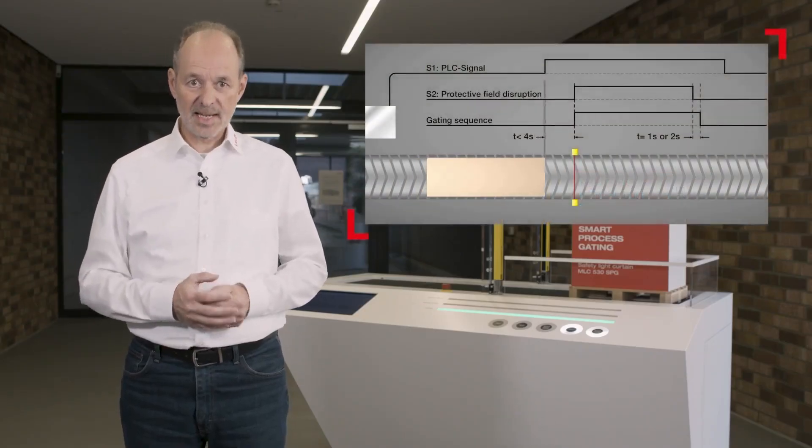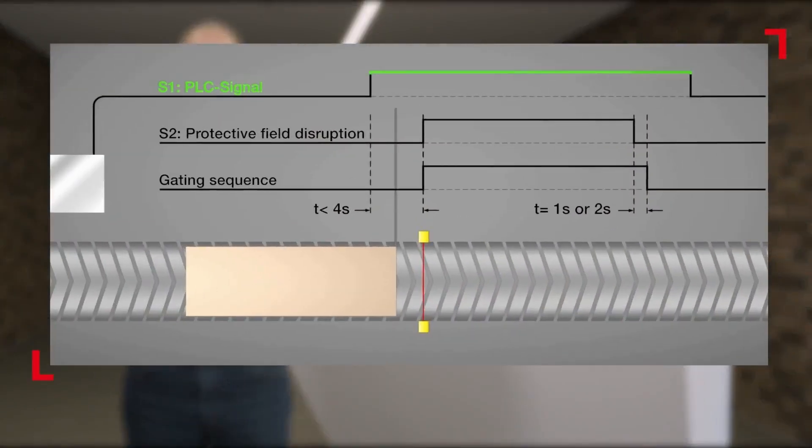What does the principle of operation look like? First, the control signal S1 is generated at this time. The goods to be transported may be not more than 200 millimeters away from the light curtain to prevent the possible slip through of a person.